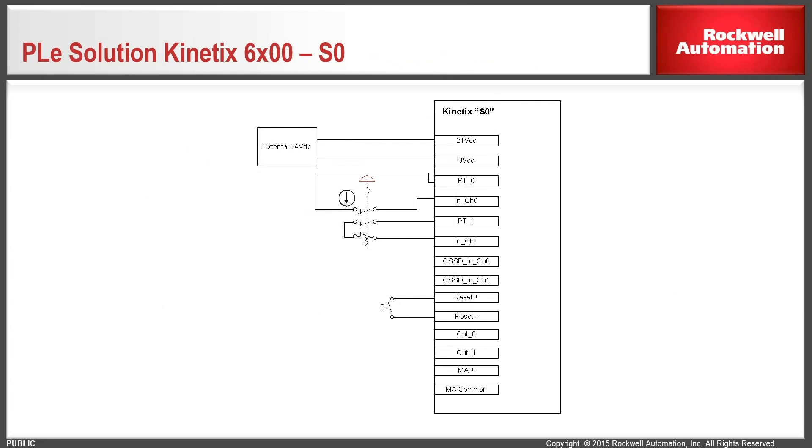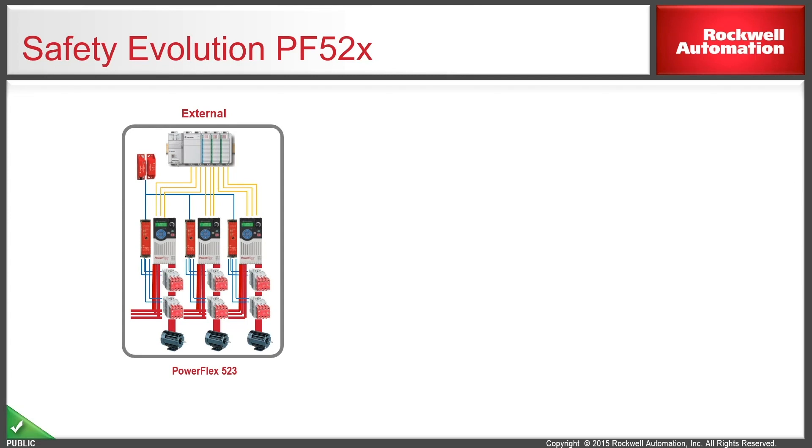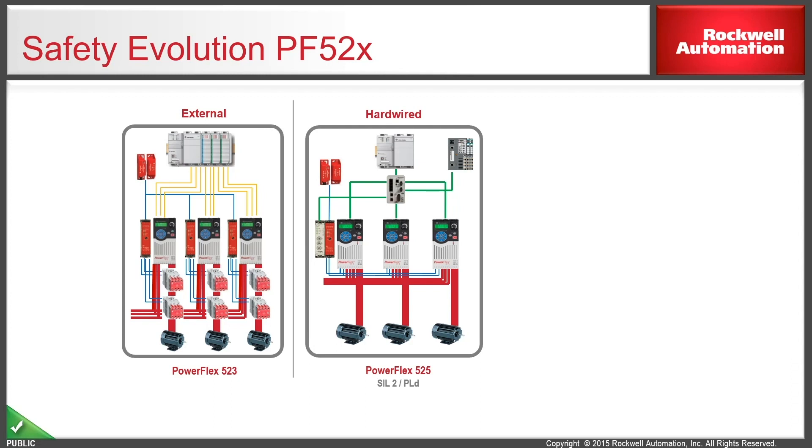With some of the newer safe torque off functionality built into drives, you still had some hardwired inputs, but it definitely was a much cleaner system. You're now basically just disabling the output circuits of the drives in a safe manner, and you're also able to cascade multiple drives together to achieve safe torque off capability. The same thing can be said for the PowerFlex 52x family of drives. If you take a look at how safety was implemented in the 523, you basically had contactors again between the drive and the motor. The 525 came out with hardwired safe torque off, so that functionality eliminated the need for the contactors. And then now with the advent of the 527, that's all done over the ethernet network, so there's no need for the safety relays and the hardware into the drive. It's all done in the safety PLC through the manipulation of tags.